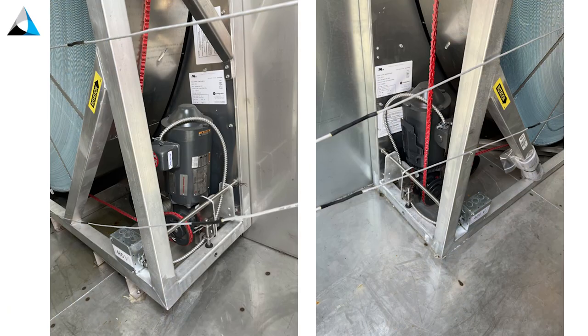On a different project, we discovered during testing that rooftop units had a separate five-horsepower motor for the heat recovery wheels that nobody knew about and wasn't connected to the main single-point connection for the rooftop unit — just a little flex cable waiting to be connected. We had to scramble to get power to those motors so the wheel would work.